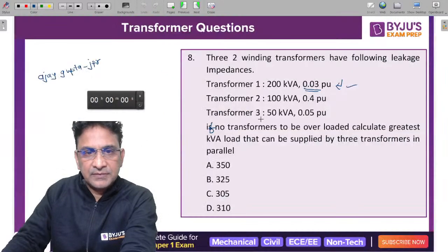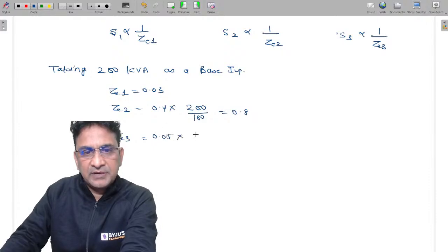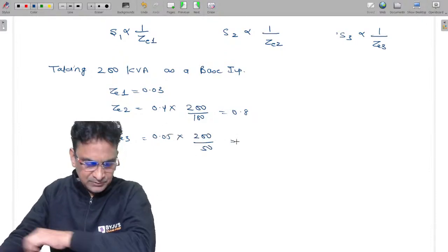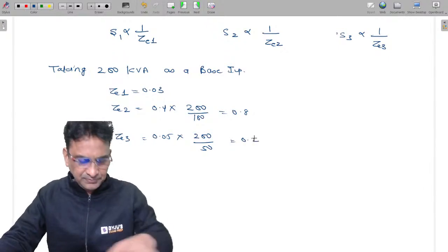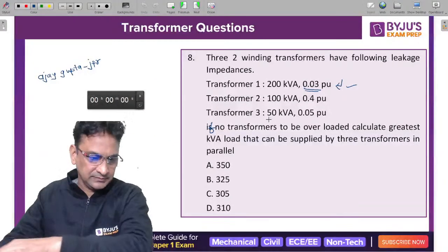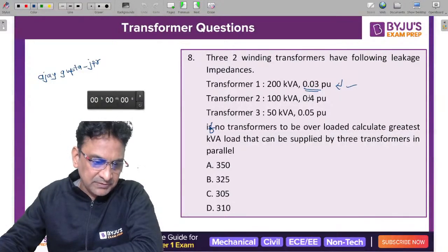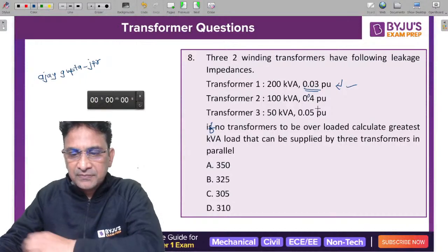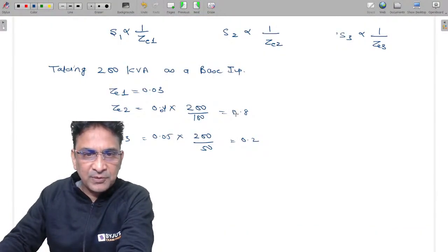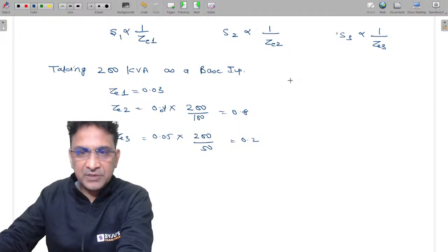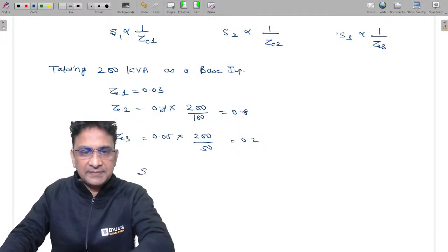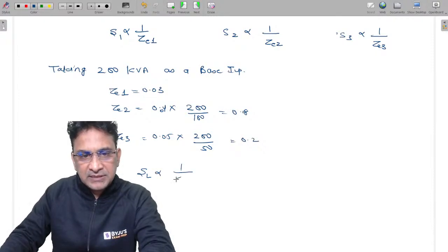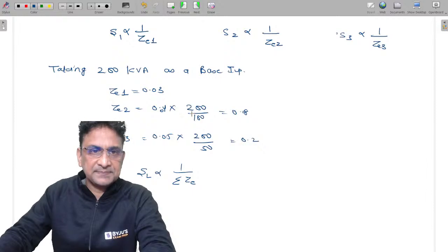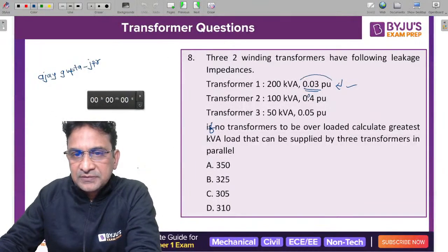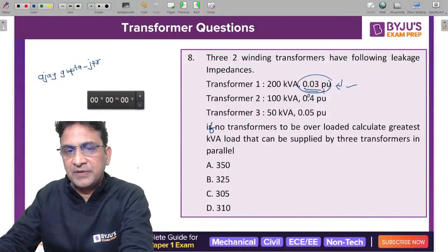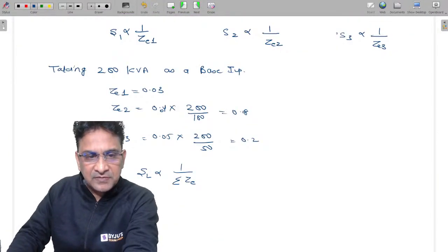ZE3, it is 0.05. Again I am converting into the 200 kVA base. So it becomes 0.2. Oh sorry, it was 0.04 pu, they wrote it wrongly here. It was 0.04 pu. So it becomes 0.08 pu. Is it clear? Now the overall load impedance SL will be proportional to the summation of all equivalent impedances. See, transformer 1 has the lowest leakage impedance value in pu, so it will be overloaded first.